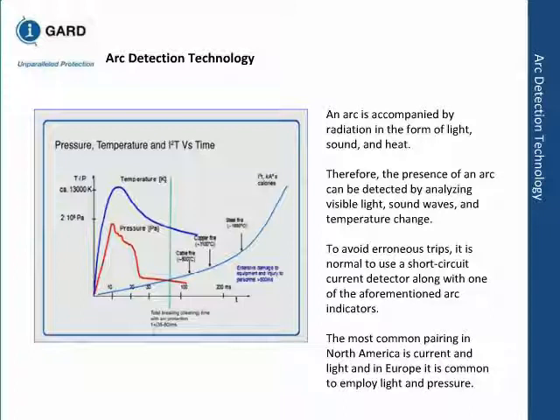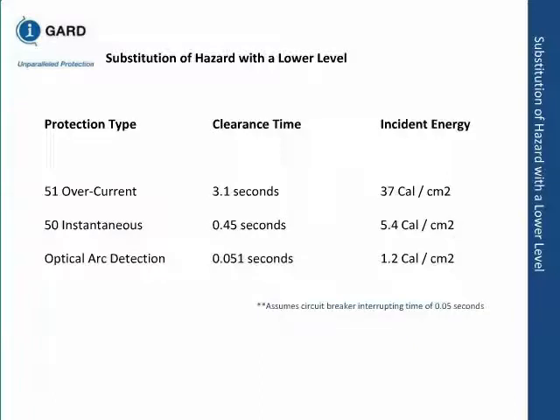Now look at the comparison with optical. If you had a typical 51 relay, which is called a timed overcurrent relay, clearing time is 3 seconds, and your incident energy is 37 calories. If you have instantaneous, you have cut down the time to about 0.45 seconds, and your incident energy dropped to 5.4. Now, if you have optical detection, you've cut down the time to 0.05 seconds. The only thing slowing it down is how fast the breaker can operate. If the breaker could operate instantaneously, it would approach zero. So with optical arc detection, you can have coordination, and you have cut down your incident energy from 37 to 1.2.